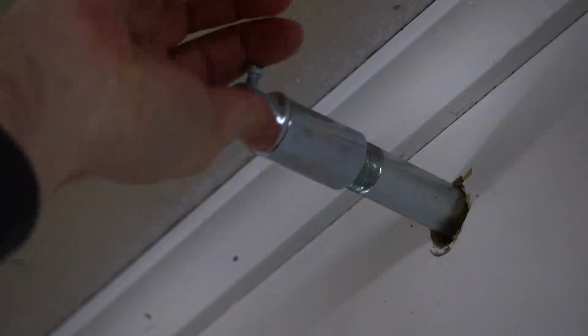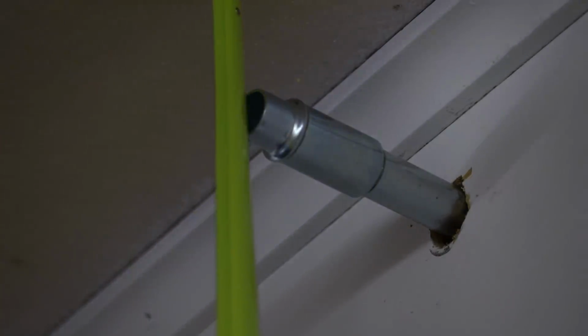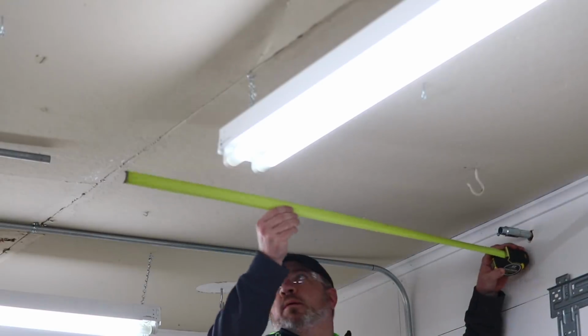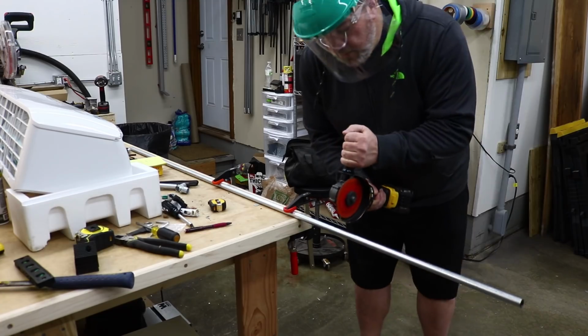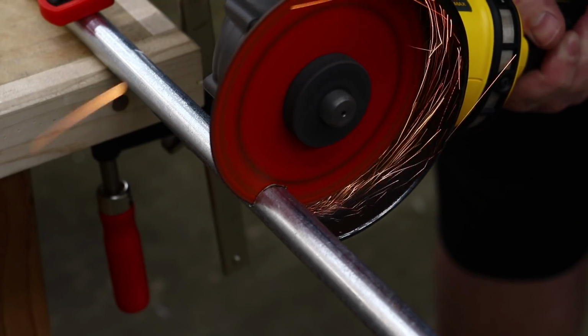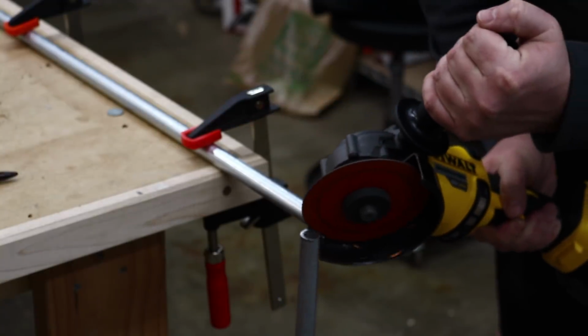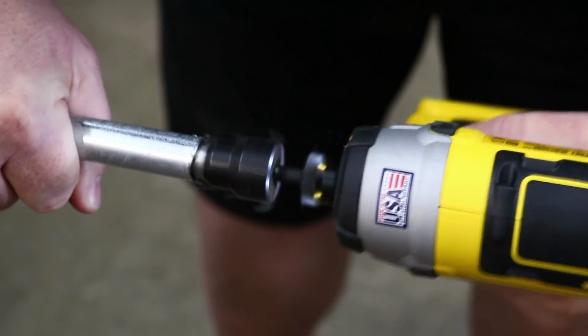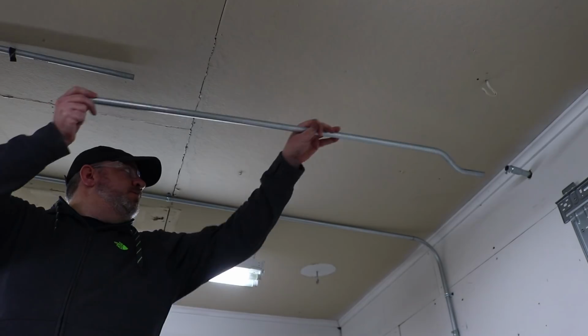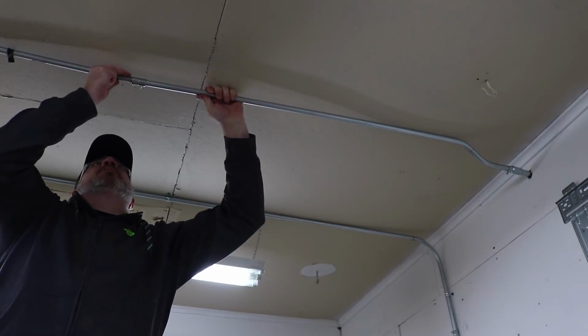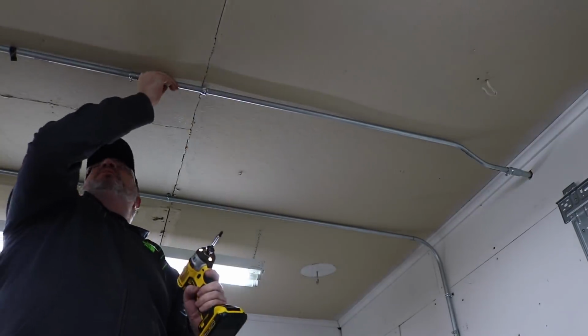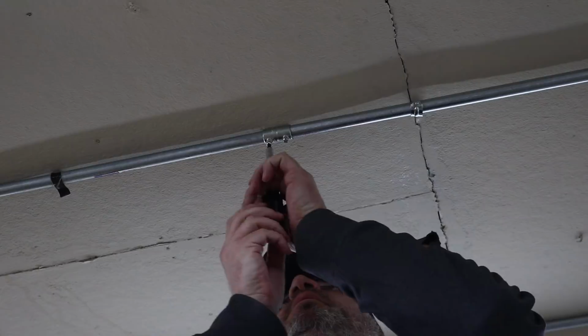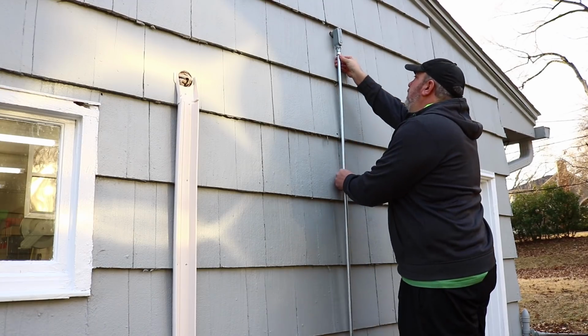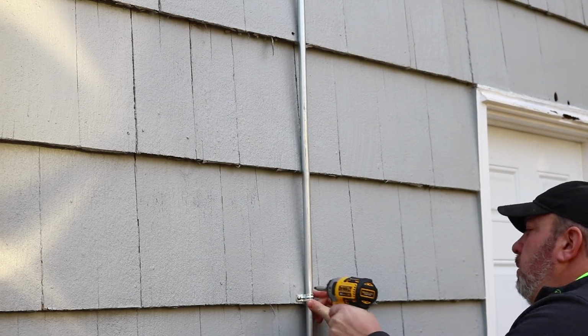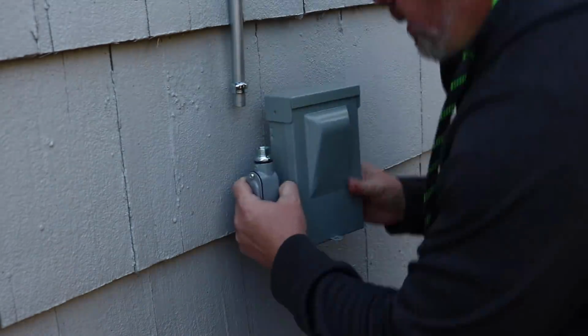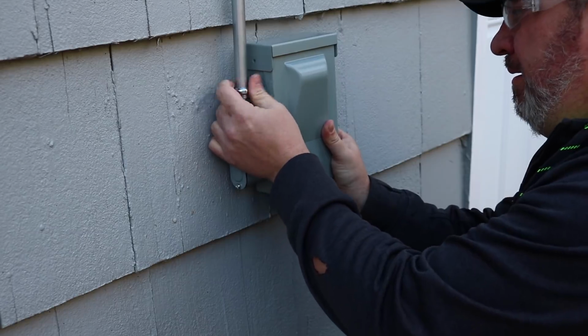Before I could install the EMT back on the outside of the house, I needed to finish the run from the sub panel over to the exterior wall. So I threaded on the galvanized coupling and a standard EMT connector, and then measured how far down from the wall I needed to make the offset, and then how long of a piece of EMT I would ultimately need. Once that piece was bent and cut to size, I could connect all 3 pieces together. With everything finished on the inside, I went back outside to attach the piece of conduit I cut earlier to the L and disconnect box, mount the disconnect box, and secure the conduit to the wall.